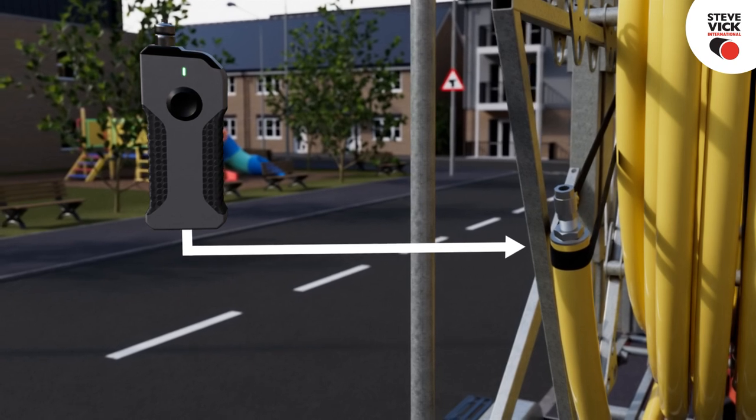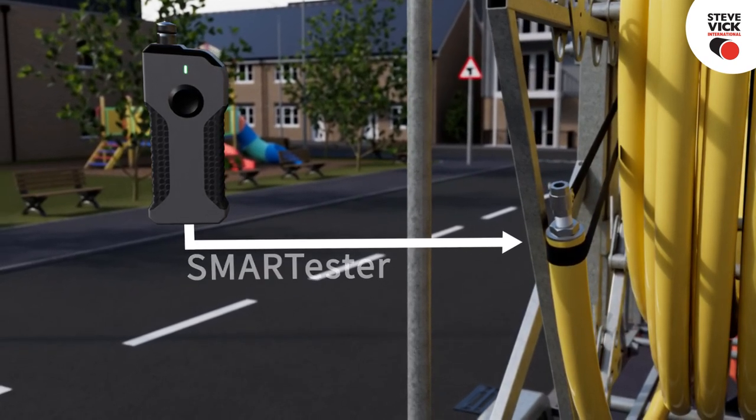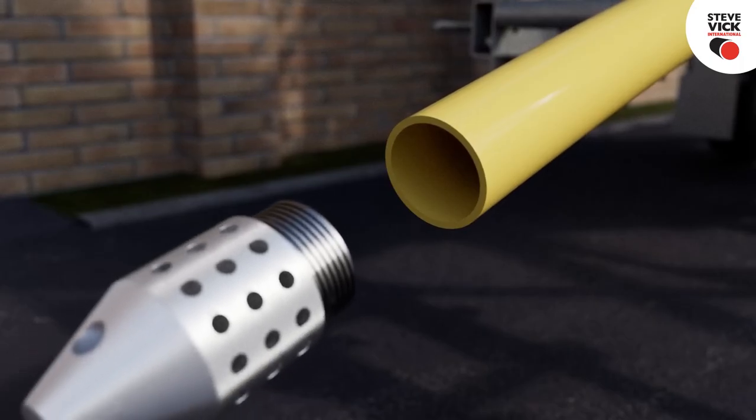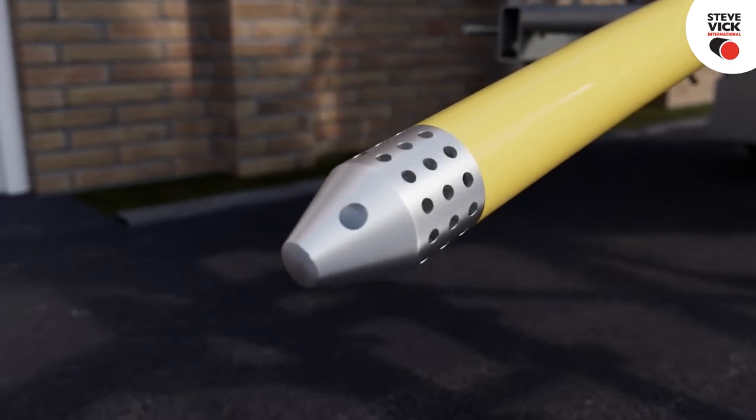Prior to insertion, the coil is pressure tested to ensure there are no leaks. This can be achieved by fitting test ends and capturing pressure data with the SMARTester. After the air has been safely released from the coil, the live head is attached to the leading end, ready for insertion.